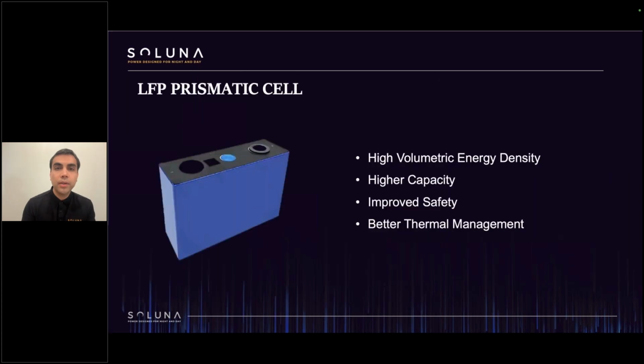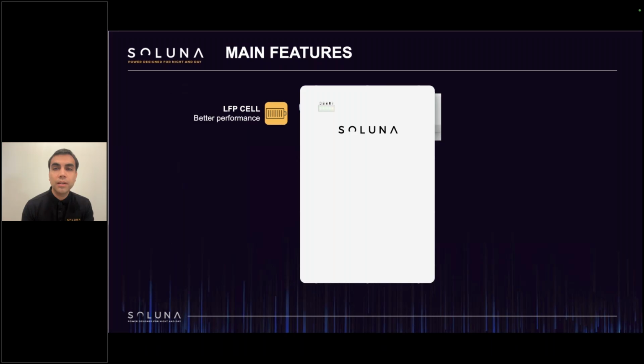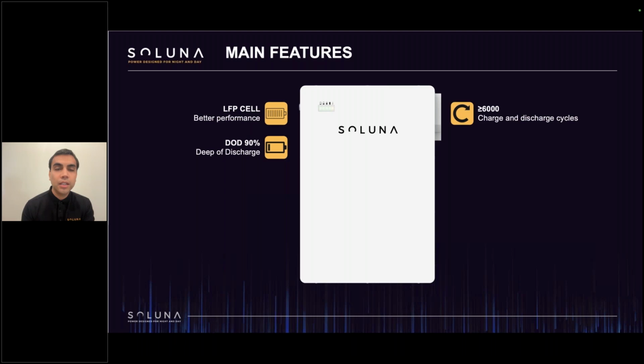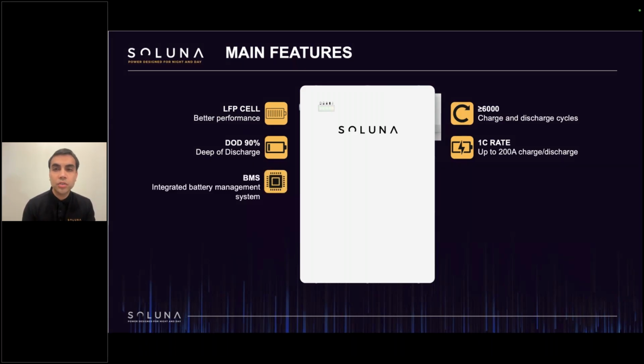And it's a lithium battery with a prismatic cell, which allows for higher capacity, improved safety, better thermal management, and high volumetric energy density. We have 6,000 cycles for charge and discharge, and the depth of discharge is 90%. If it's an off-grid scenario, we recommend 80% for the depth of discharge. It's 1C rated, which allows you up to 200 amps charge and discharge.